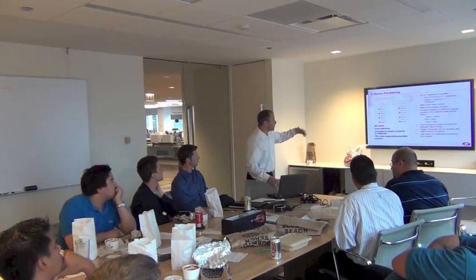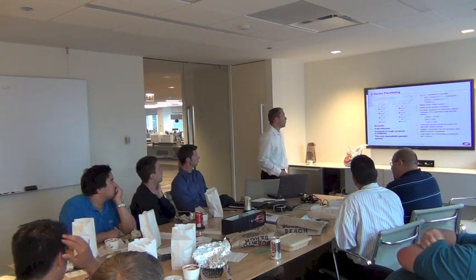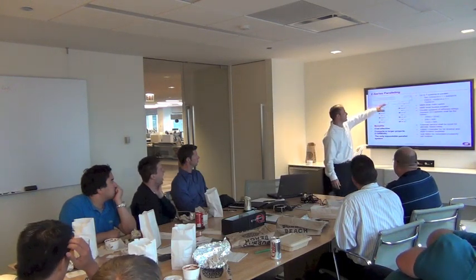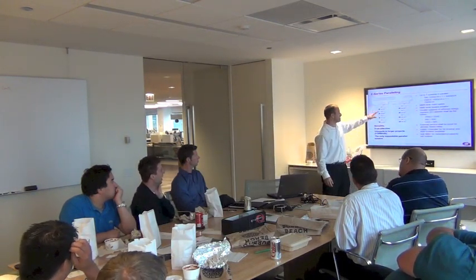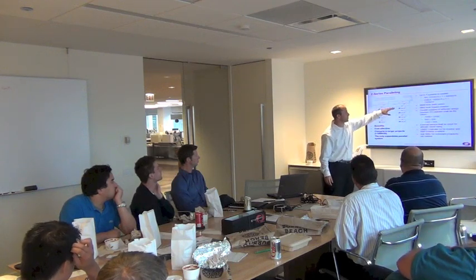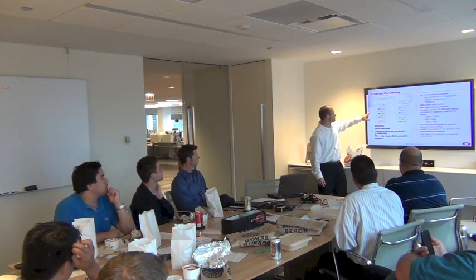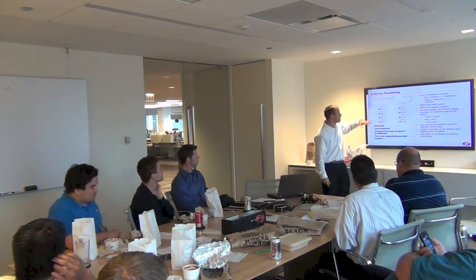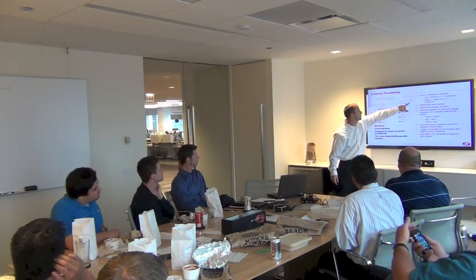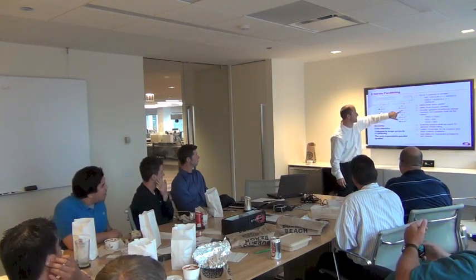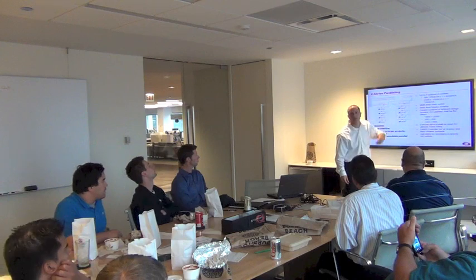So this is basically just showing an example of how we parallel. We can do basically a distributed bypass or a centralized. This is an example of paralleling 2 UPSs with a distributed bypass. These input breakers will be in the same board, not the greatest drawing. These will be in the output. You have an output isolation breaker for each UPS, you have a tie breaker, then you have a maintenance bypass breaker.